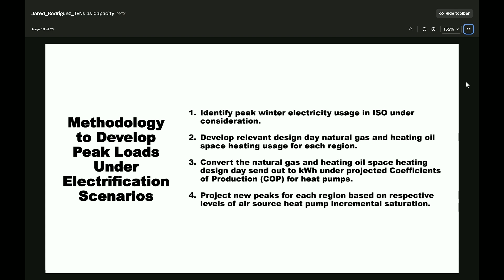So we asked, what does it look like if you shift the peak into the winter? At what point does the winter peak exceed the summer peak? Here's an example of converting 20% of natural gas use and 80% of current oil use in New York, using an average COP of 1.5 at the low temperature during that peaking period.